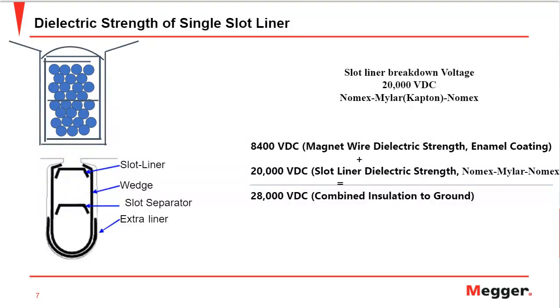So, the dielectric strength of the slot liner. On the screen you can see 28,000 volt DC is the combined insulation to ground for a 460 volt motor. For any pure electrically insulating material, this is the maximum electric field the material can withstand under specific conditions before electrical breakdown, or it can avoid becoming electrically conductive. So the total insulation between one single copper conductor of a 460 volt motor and the core of the motor is a total of 28 kV DC, or 28,000 volt DC. That comprises two parts.